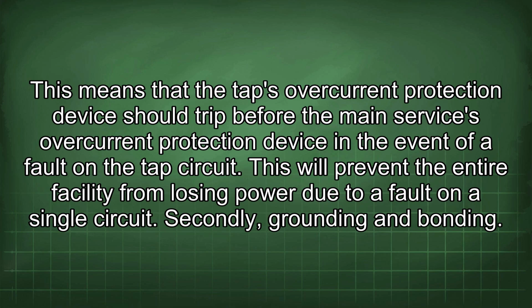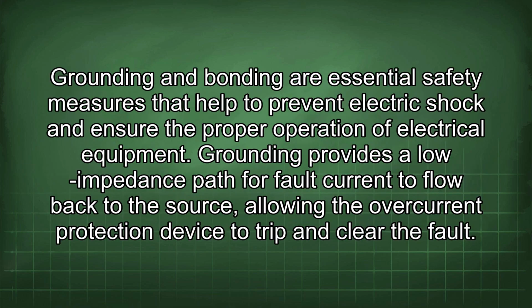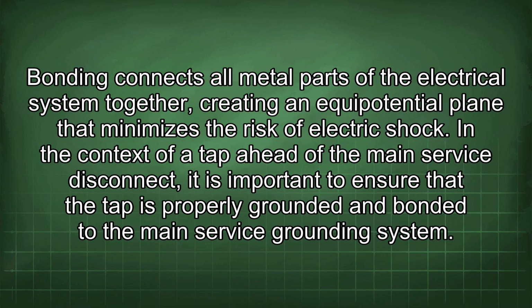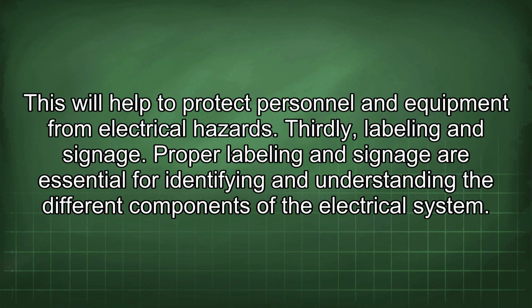Secondly, grounding and bonding. Grounding and bonding are essential safety measures that help to prevent electric shock and ensure the proper operation of electrical equipment. Grounding provides a low impedance path for fault current to flow back to the source, allowing the overcurrent protection device to trip and clear the fault. Bonding connects all metal parts of the electrical system together, creating an equipotential plane that minimizes the risk of electric shock. In the context of a tap ahead of the main service disconnect, it is important to ensure that the tap is properly grounded and bonded to the main service grounding system. This will help to protect personnel and equipment from electrical hazards.